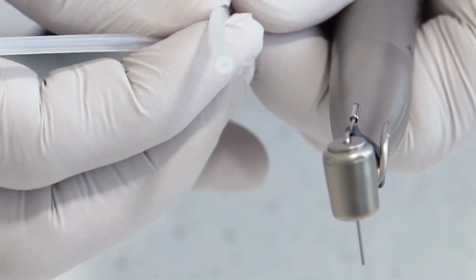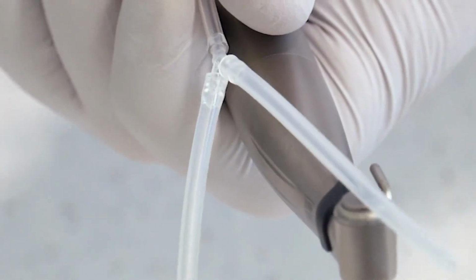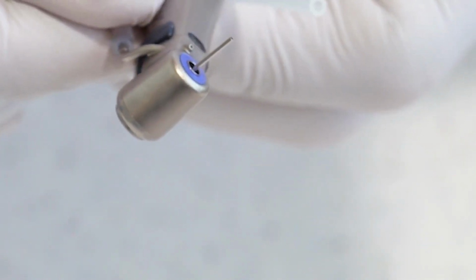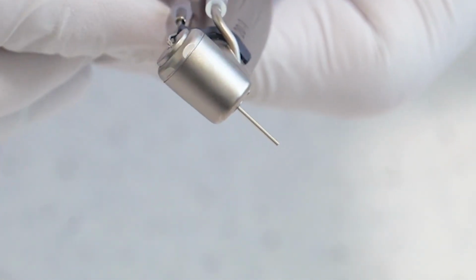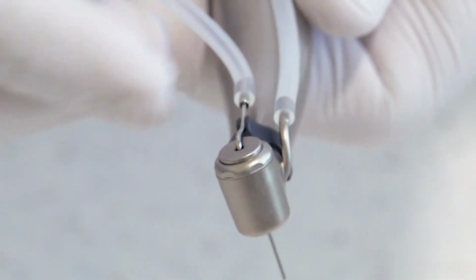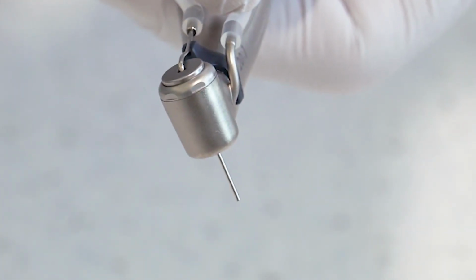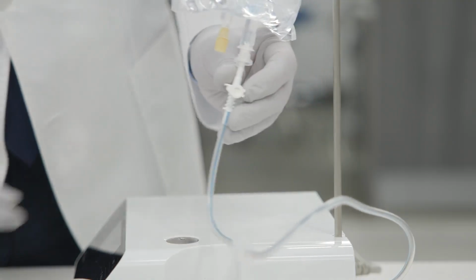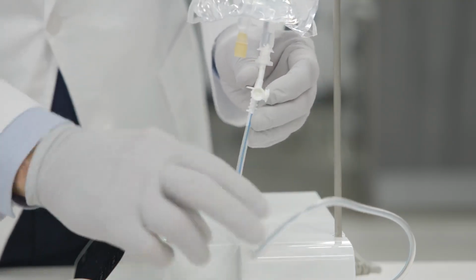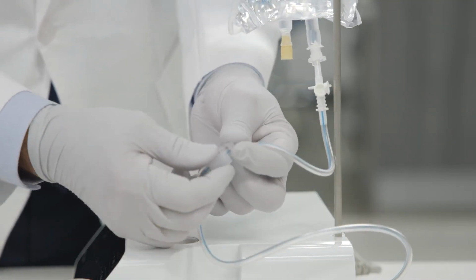Simply connect the Y connector to the end of the main irrigation tube. Then connect one of the water supply tubes to the external spray nozzle so the free end of the Y connector is connected to the internal spray nozzle. This dual irrigation setup is only used in unique cases with certain drills. Now open the tube clamp and the air cap. You're ready for operation.